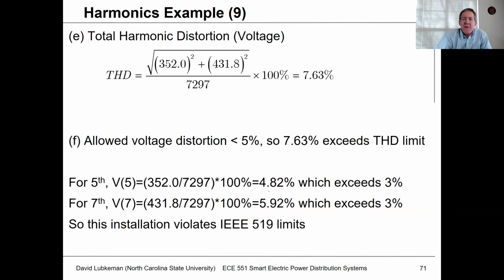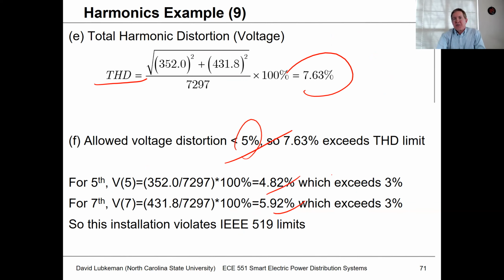So anyway, once you have these numbers, you can get the THD. We see the THD is too high. The allowed distortion level is just 5%. So there would be something we would need to do about this. We're exceeding the total harmonic distortion. We're exceeding the individual limits. And so this is clearly a non-compliant type of load case for this particular situation.